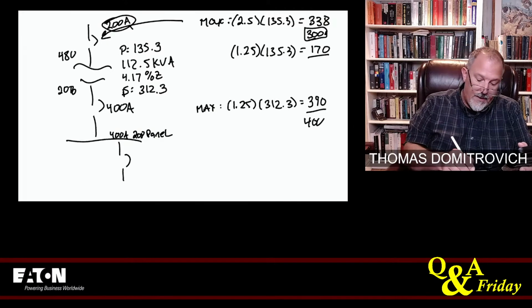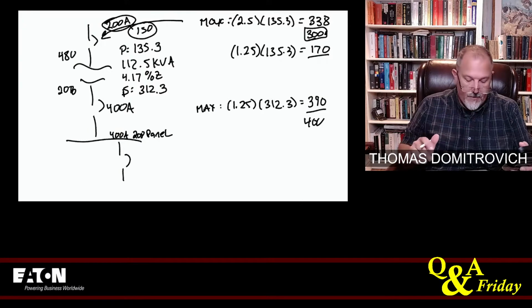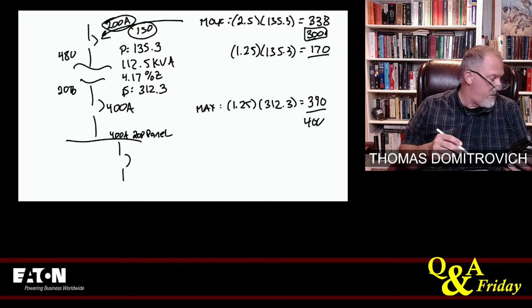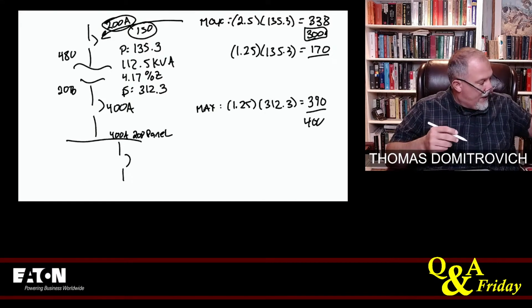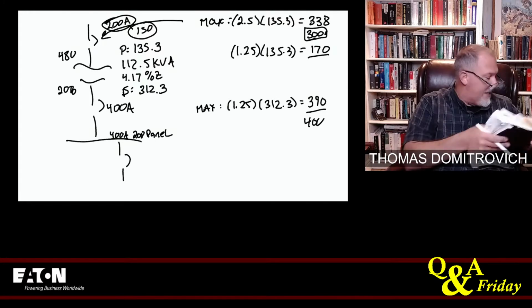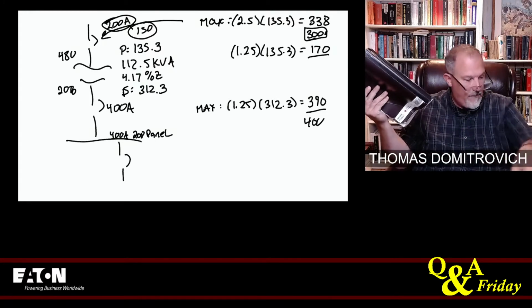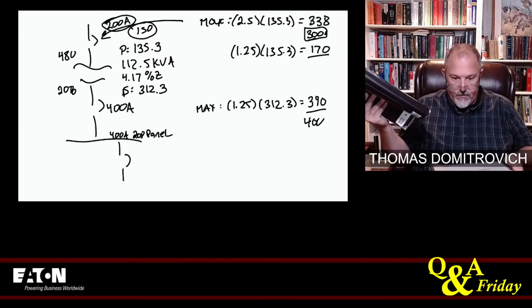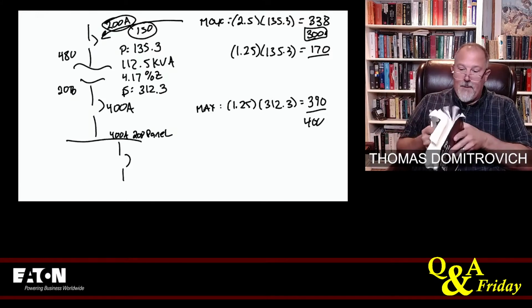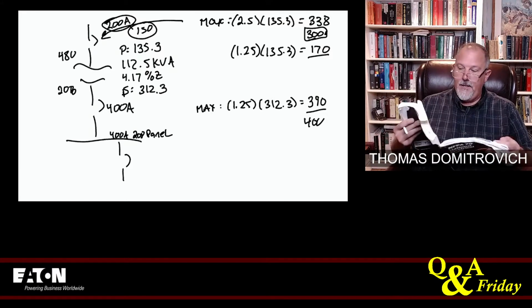Or maybe even a 150. I don't know. We'll take a look in that ballpark once I get on SKM. All right, so I know my secondary, and then my conductors. I have to have enough ampacity. Just lost my tap rules. I have to have enough ampacity, so I'm going to go to 310.